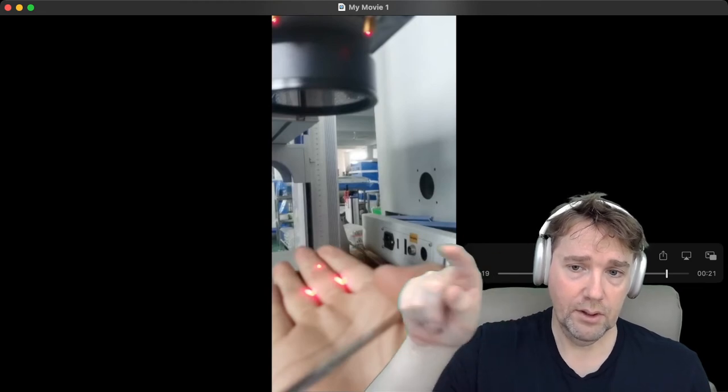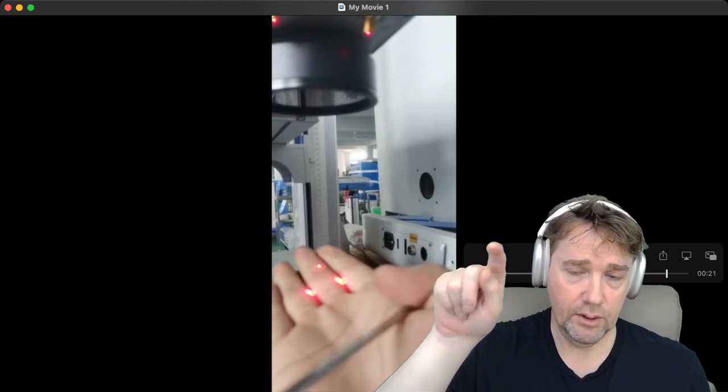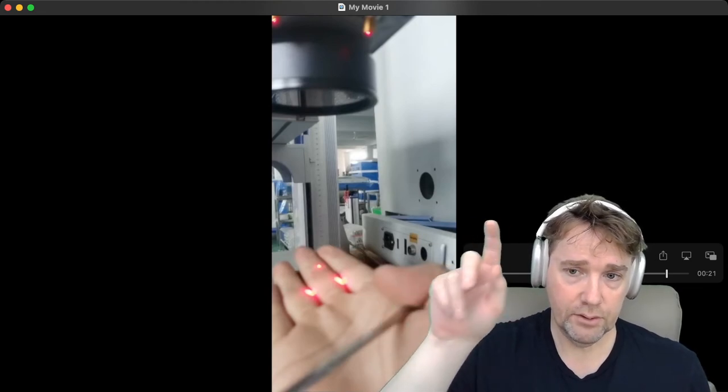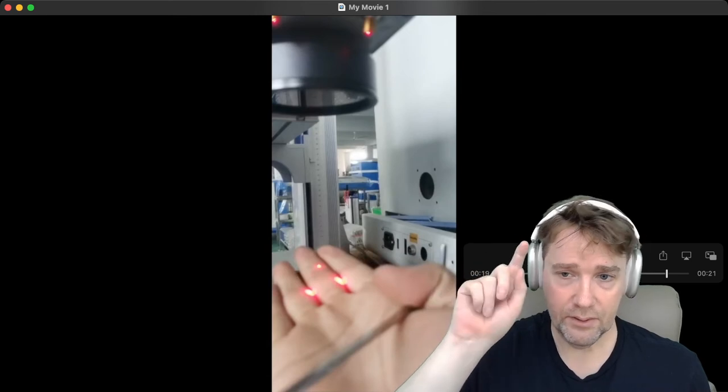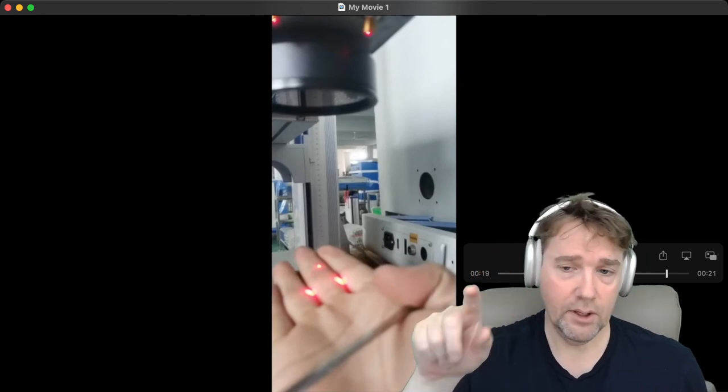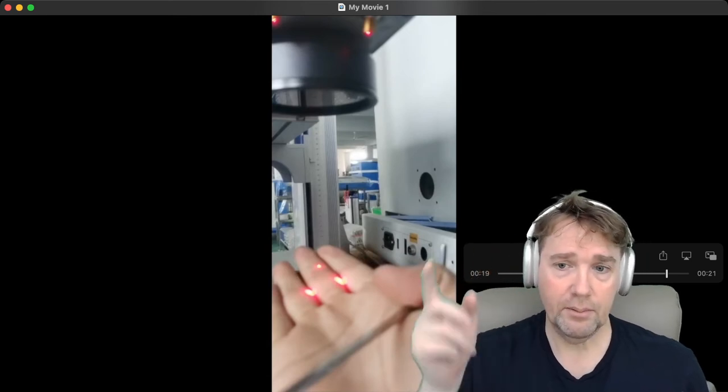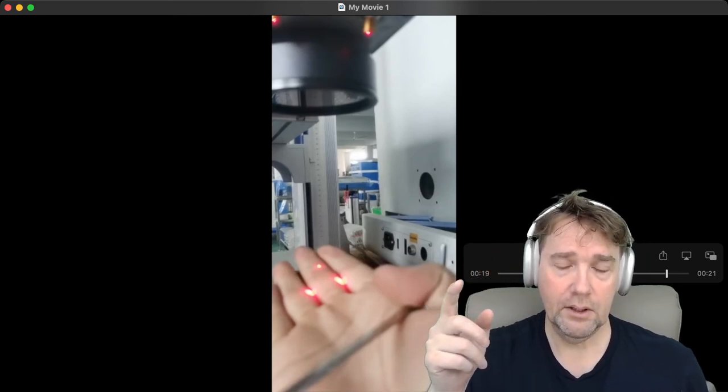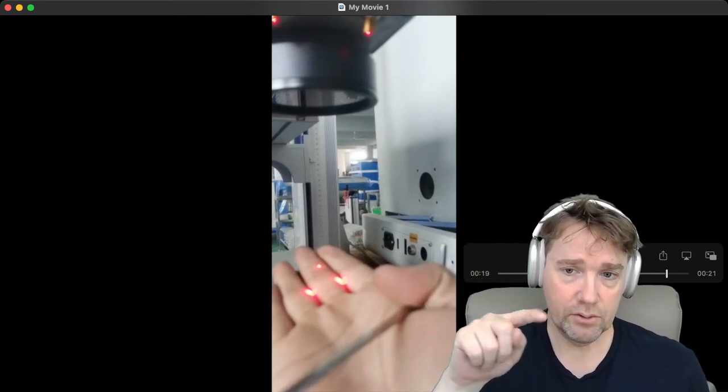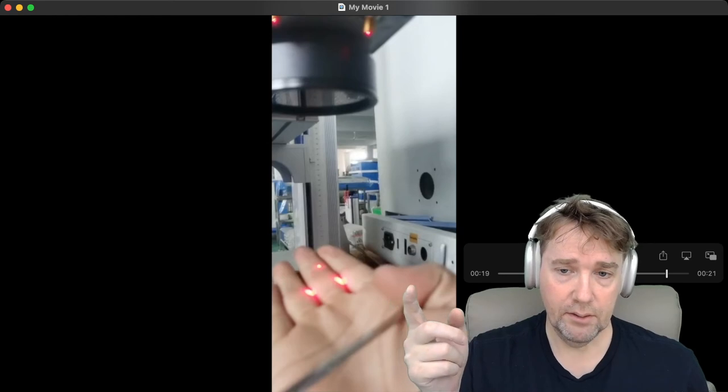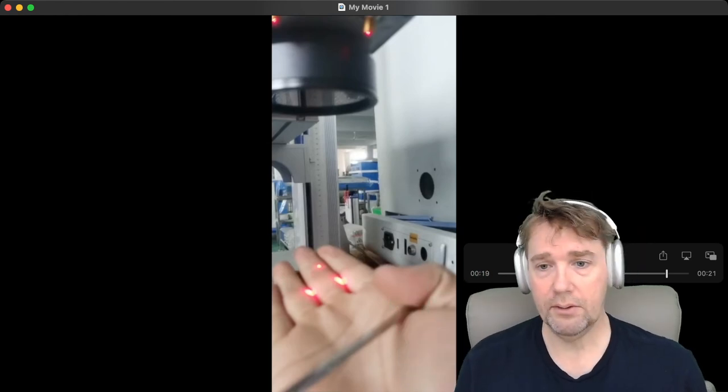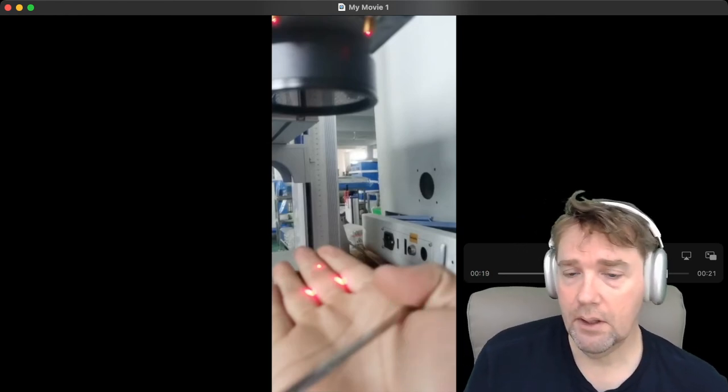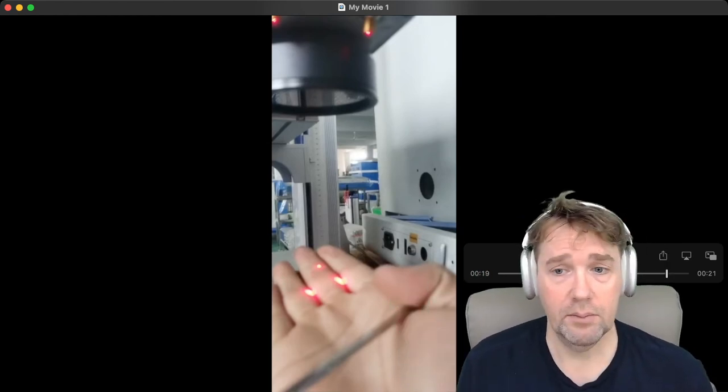If those lasers are on and your galvometer is not working, then the galvometer is dead. If those lasers are not on, then at least you need to replace your power supply. This is how you debug if the failure is in the power supply or in the galvometer head.